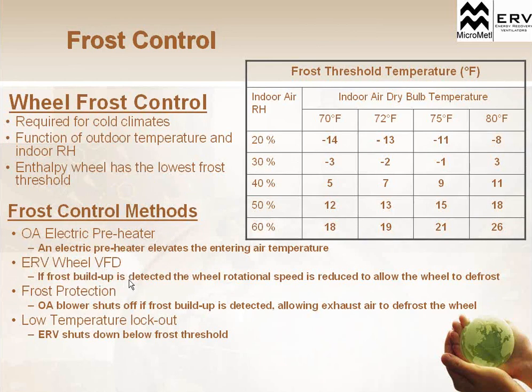ERV wheel VFD. We can actually slow down the rotation of the wheel, meaning more of that return air would have a longer time to defrost the wheel. The frost protection is when the outside air shuts off. We close the dampers to the outside air, allowing a recirculation of the exhaust air in the wheel, so that would defrost the wheel as well. Or we can have a low temperature lockout, so whenever we go below that threshold with that humidity level, we can lock out the ERV itself and just go into a full economizer mode, or reduce that to the minimum ventilation requirement for that space.